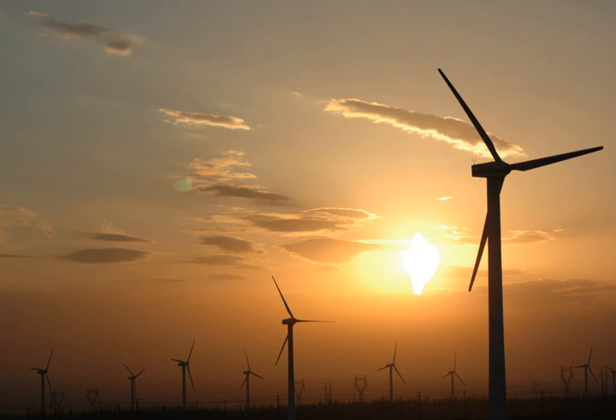Transmission system operators will supply a wind farm developer with a grid code to specify the requirements for interconnection to the transmission grid. This will include power factor, constancy of frequency and dynamic behavior of the wind farm turbines during a system fault.